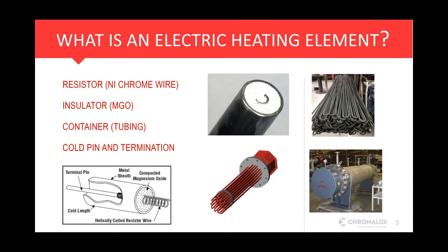The basics, of course, is what is electric heat. The core technology is really pretty straightforward, comprised of four major components: the resistance wire, which passes the current and generates the heat; the dielectric insulation material, which isolates and protects that resistance wire; the container, the metal sheath that protects the internals; and the cold pin and termination, which allows you to apply power to the element. So that's really what an electric heater is.